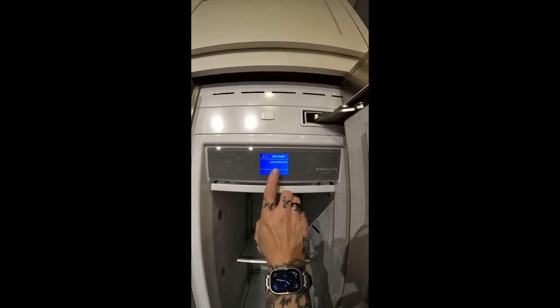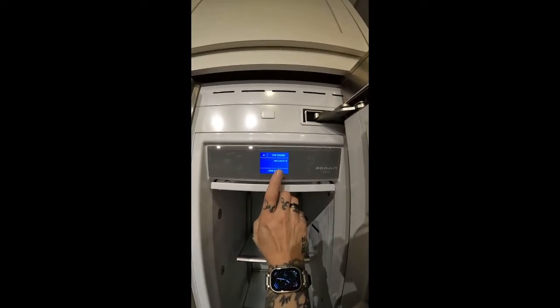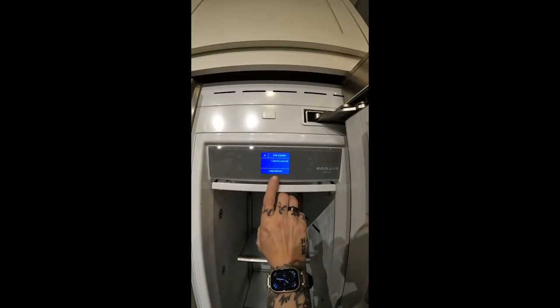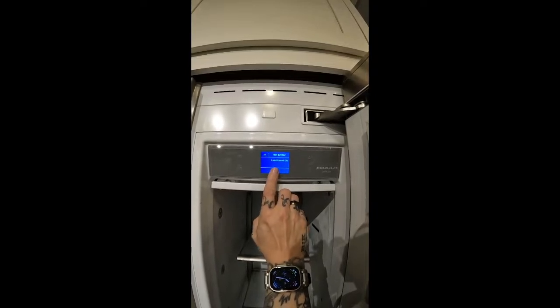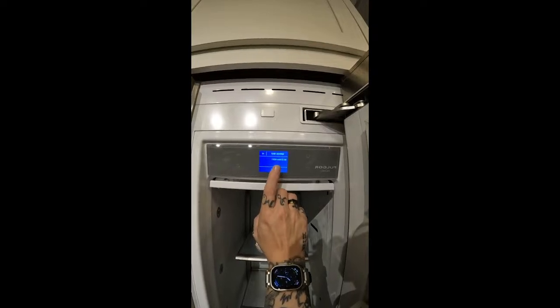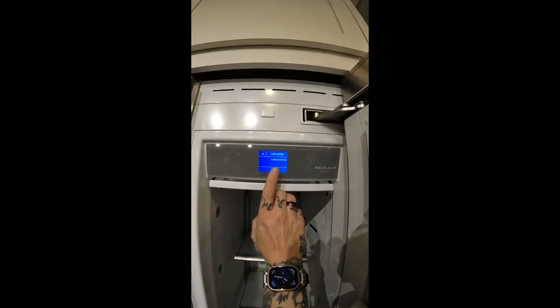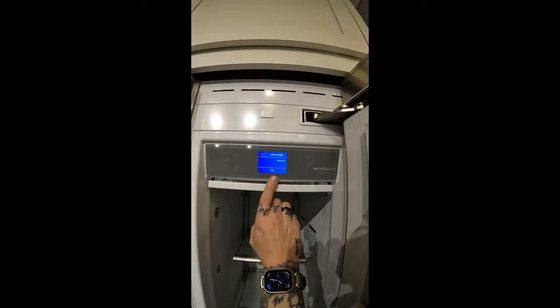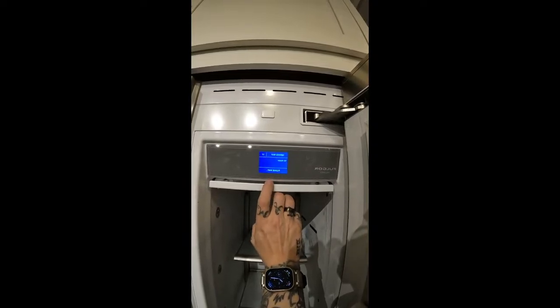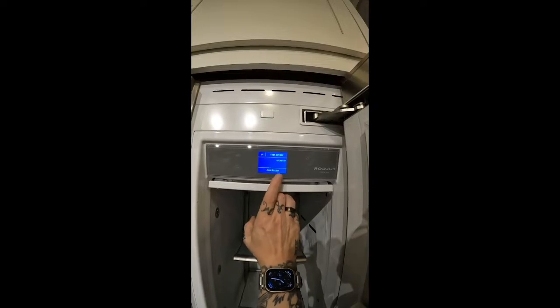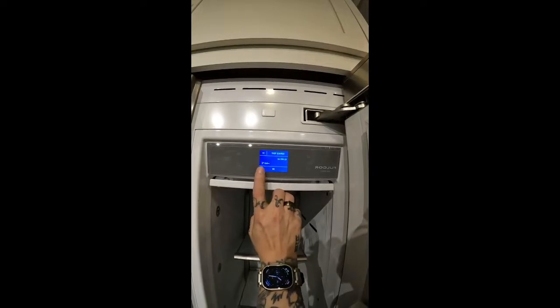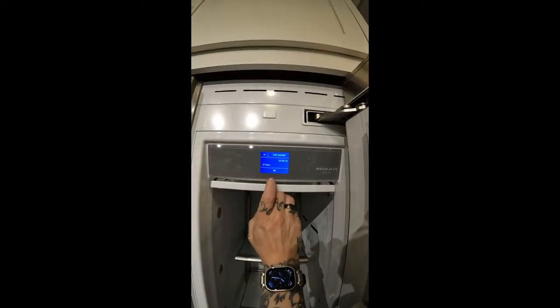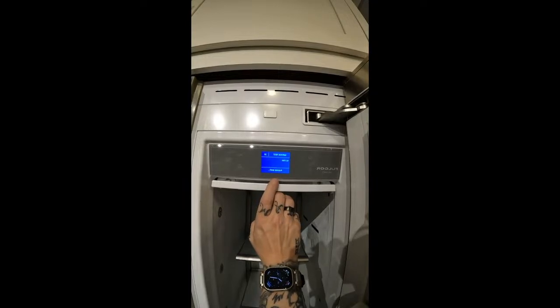V3 ice maker heater is your fill tube heater. This does not have a switching valve. It's a freezer column. You can check each valve independently. Manual clean will open them both together so you get water flow. V1 heater is not used as a freezer column. V2 heater is not used as a freezer column. It shows -40 because it does not exist. V2 is a fridge. Same idea there.